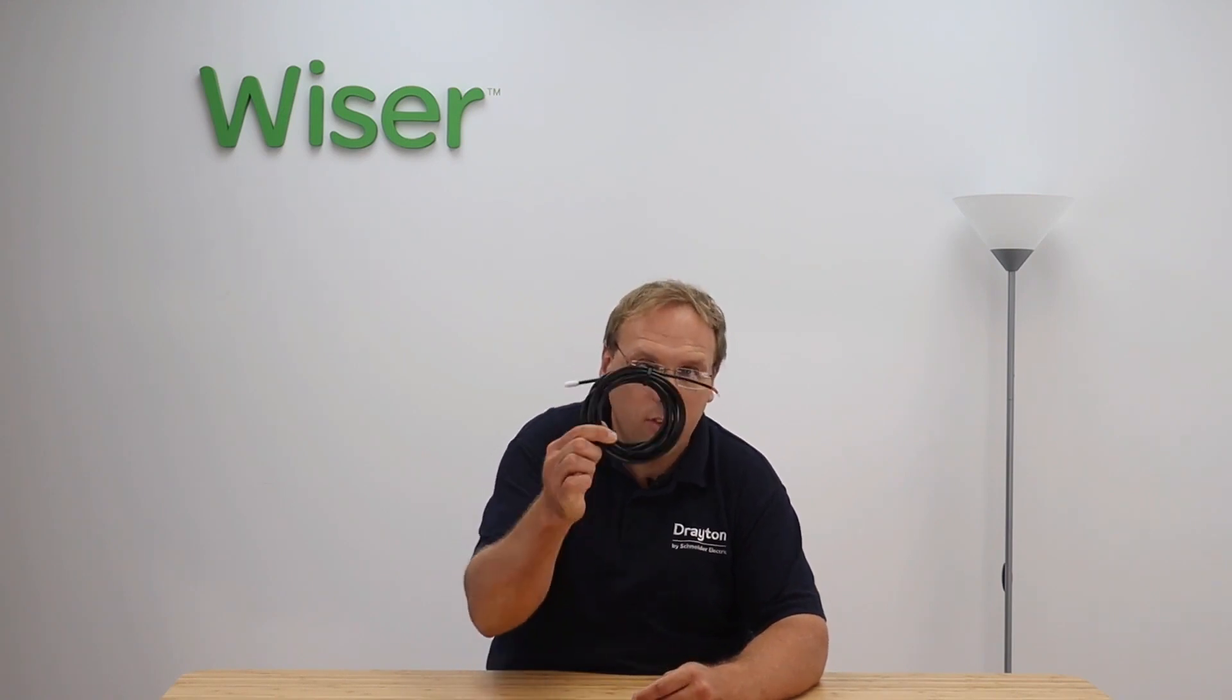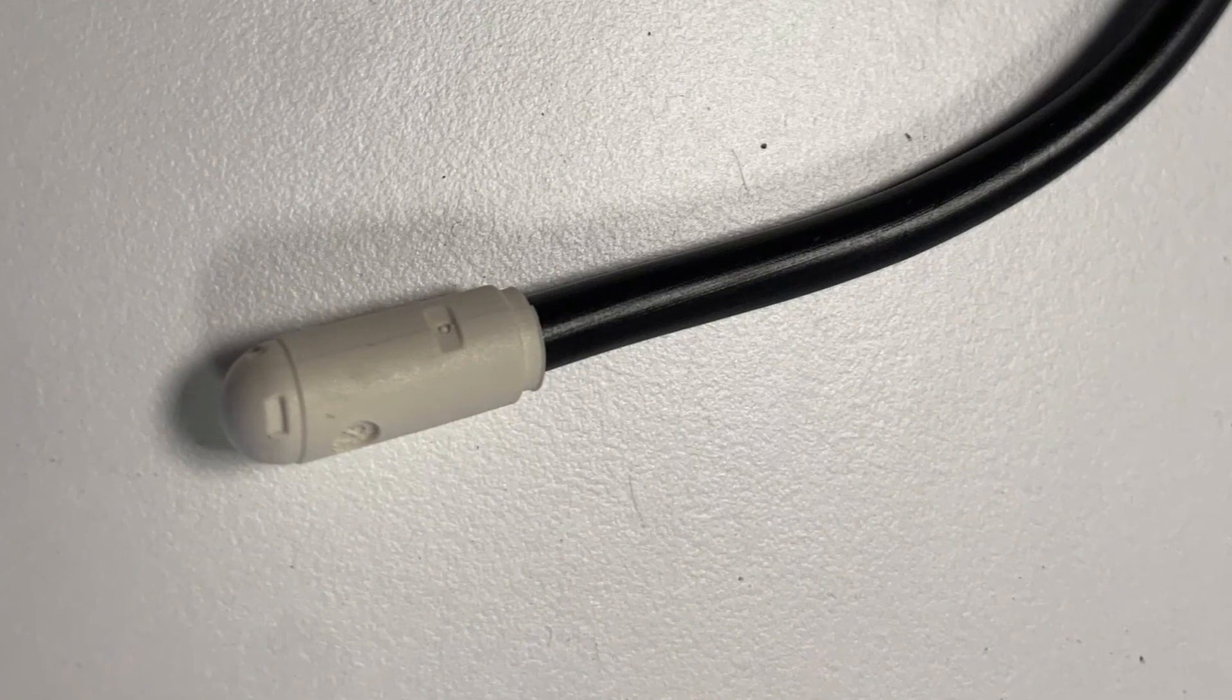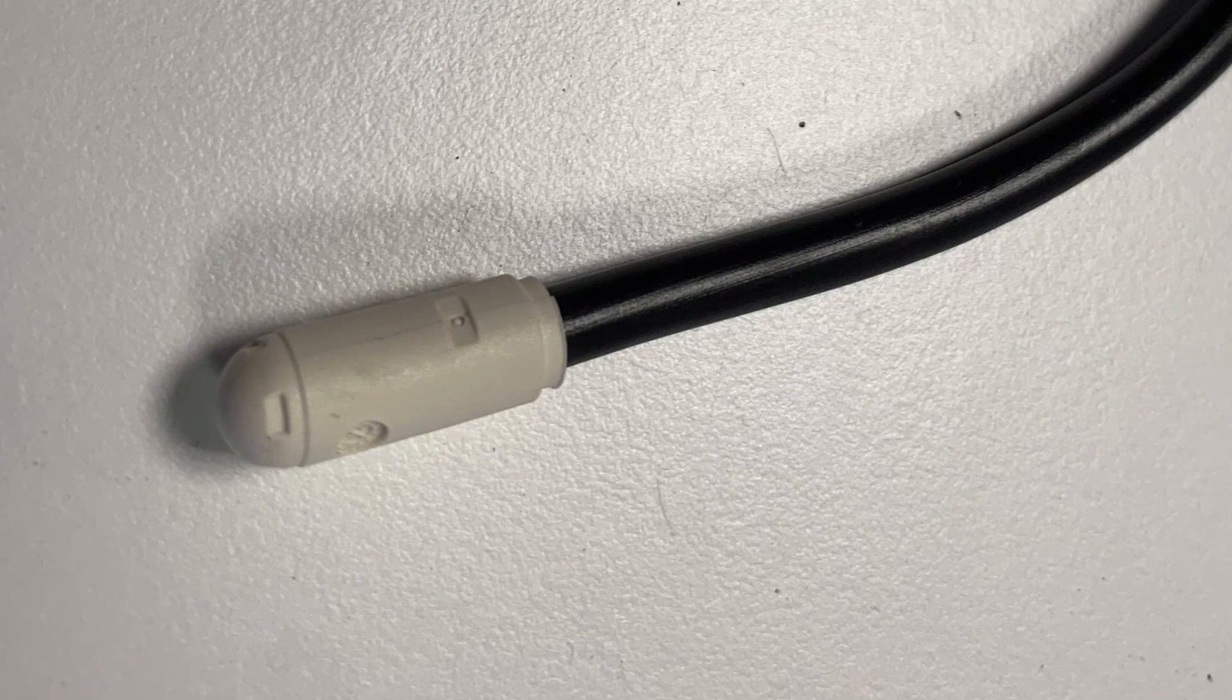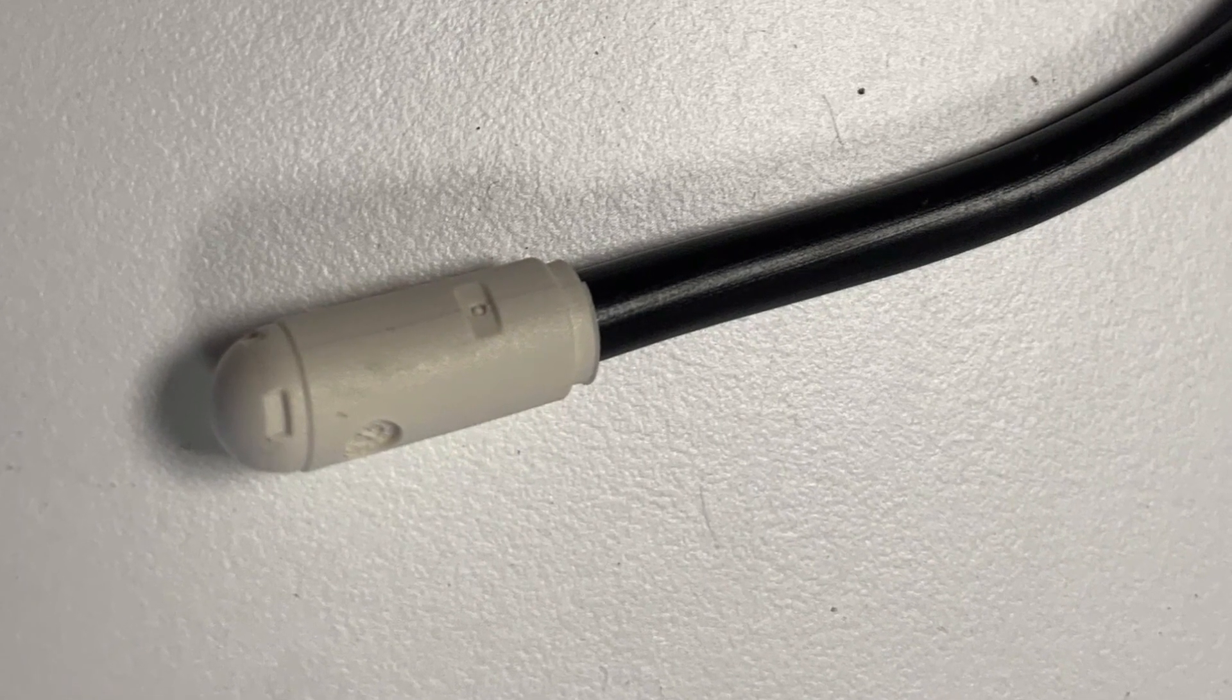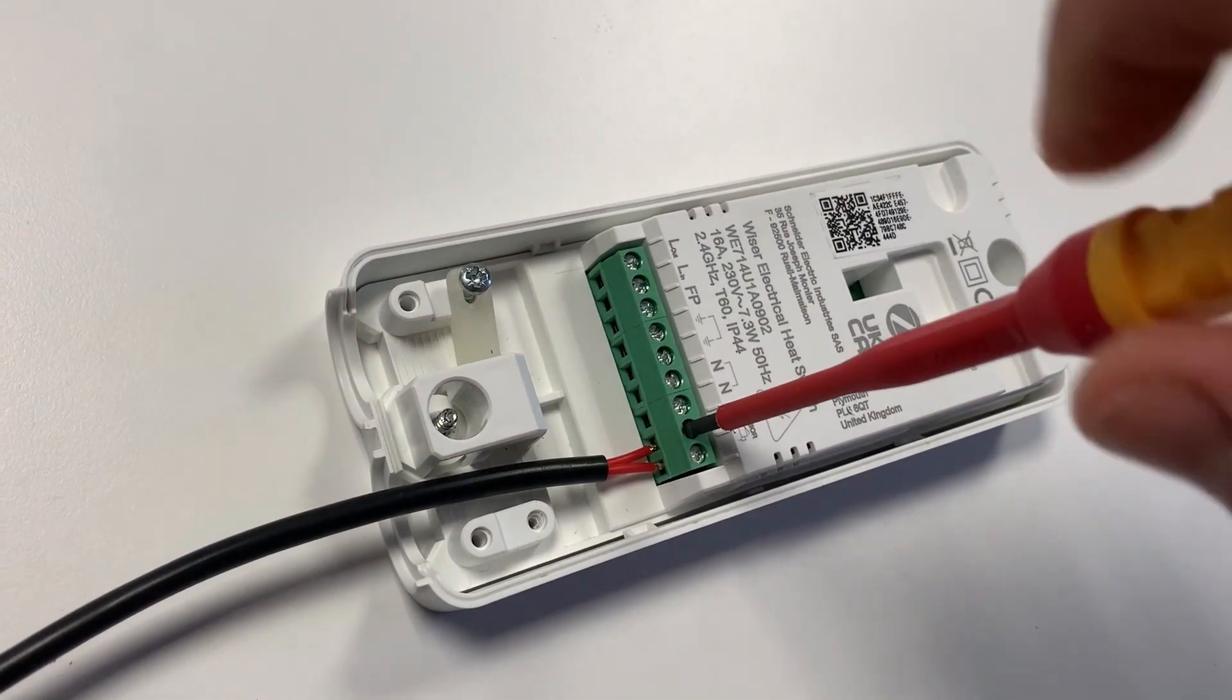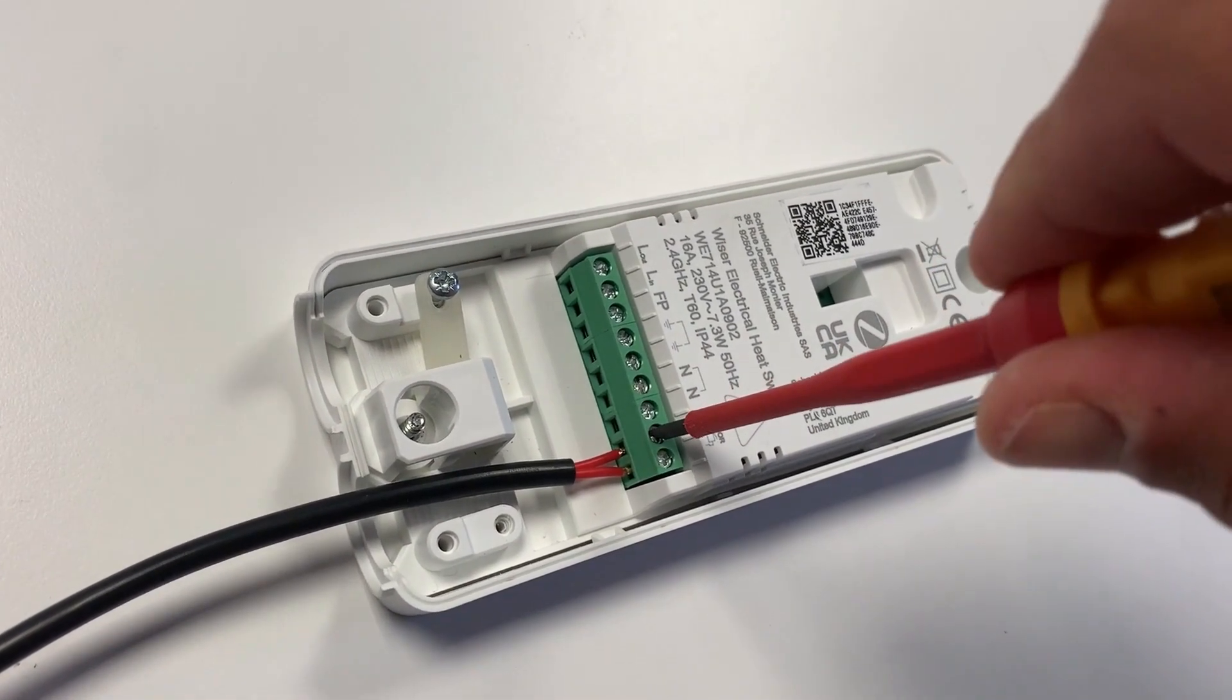As I said earlier, if you're using this to control electric underfloor heating, it's mandatory that you connect one of these: our room floor sensor. The end that's got the white bulb gets buried in the floor and typically goes between the elements on the underfloor heating mat. The other end wires into the two terminals on the electrical heat switch itself.